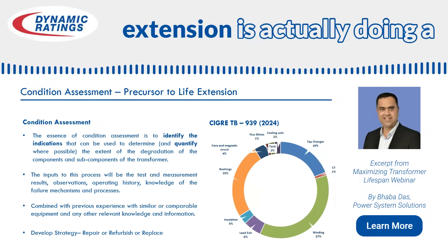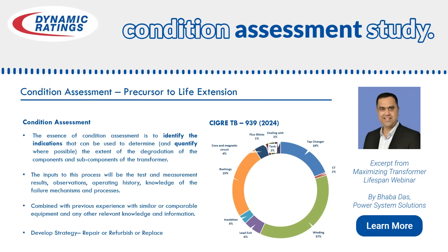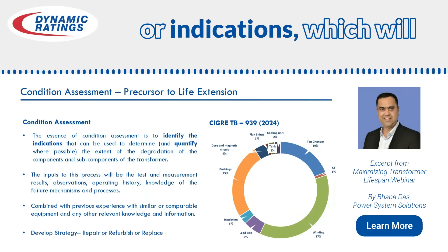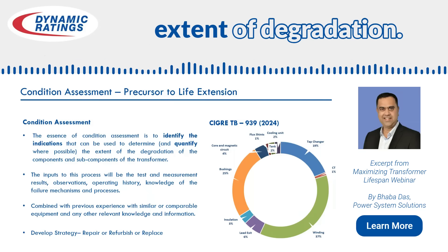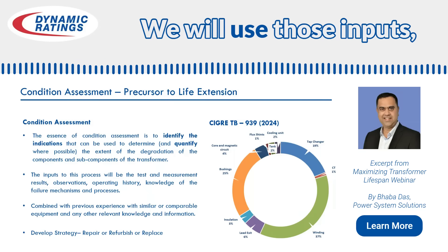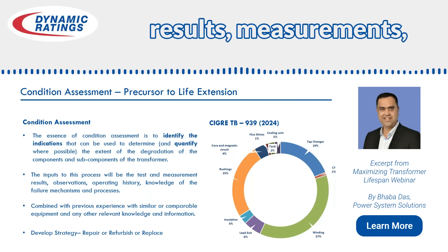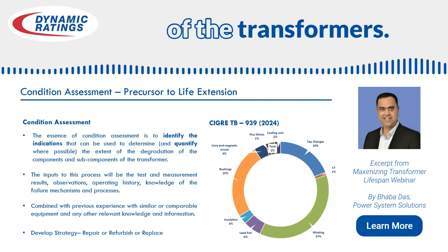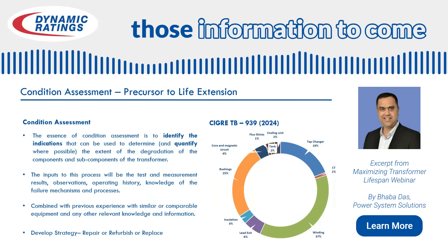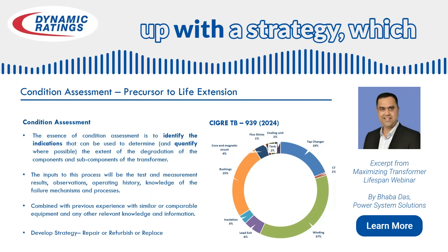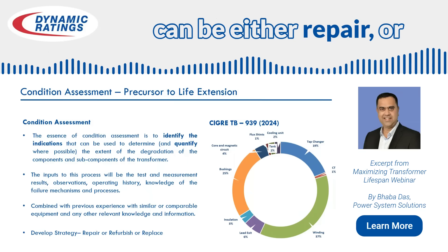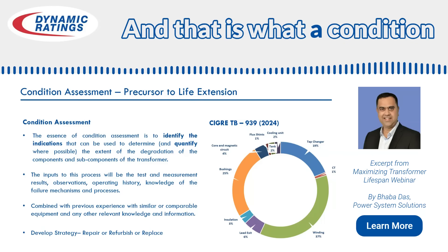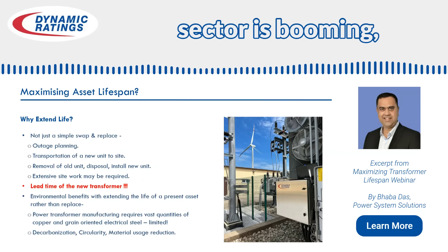The precursor to life extension is actually doing a conditional assessment study. It is to identify those signs or indications which will help us to determine the extent of degradation. We will use those inputs — our results, measurements, visual inspections, our knowledge of the history of the transformers — and then use all of that information to come up with a strategy, which can be either repair or refurbish the transformer, or replace the transformer. That is what a conditional assessment is all about.